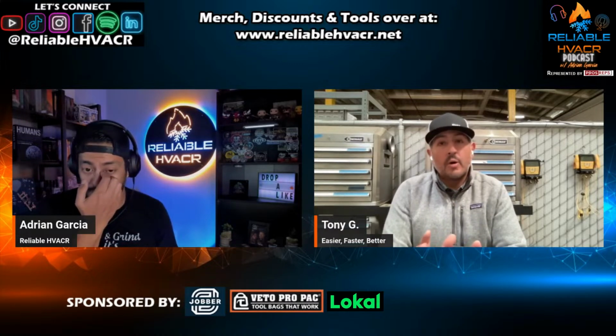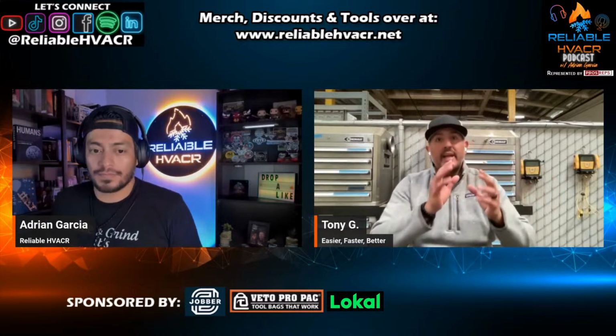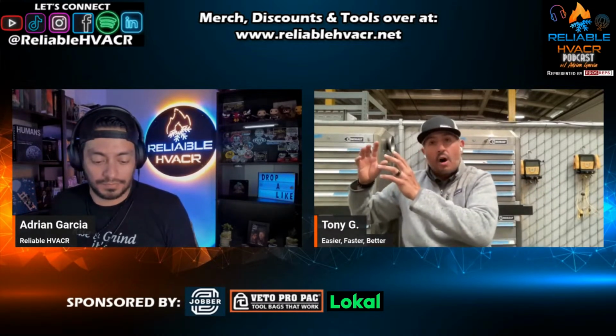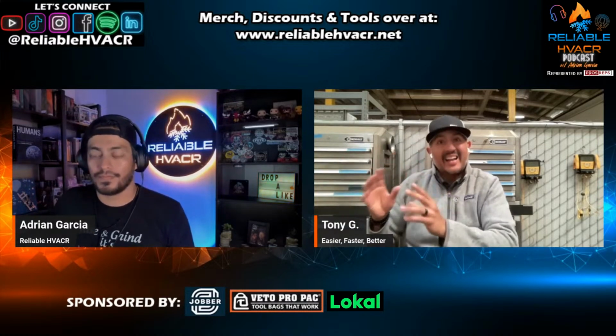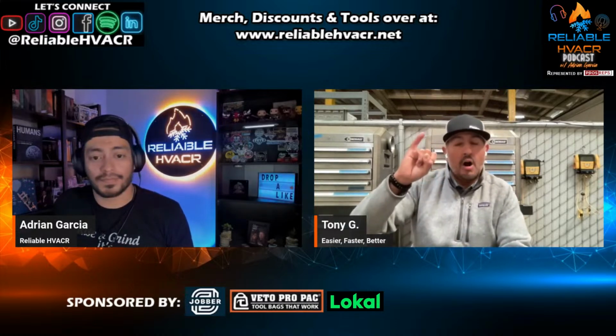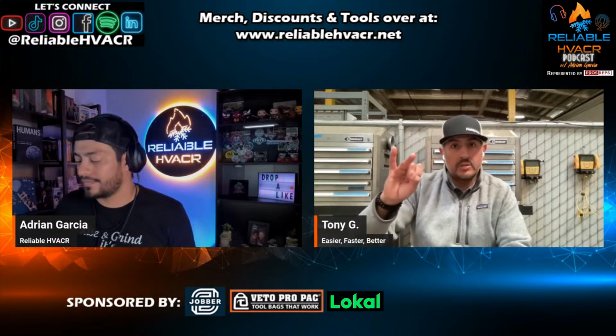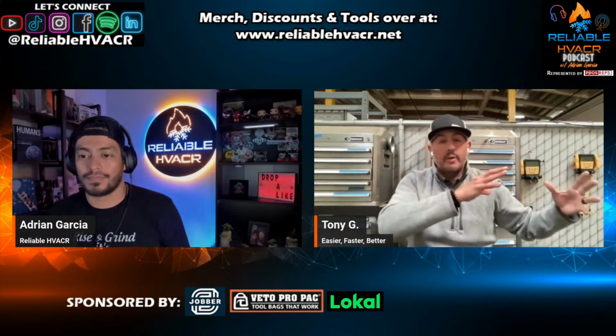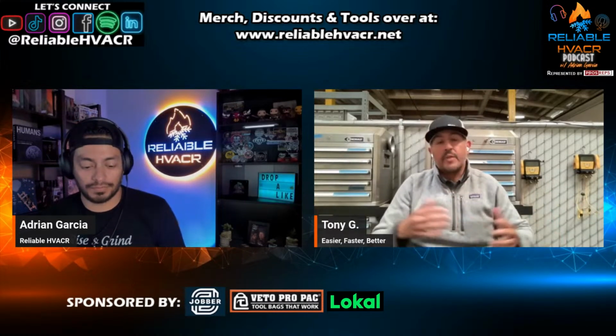And for those that were in the field when we had to transition from R22 to 410A, this transition from 410A to the R454B or things like that is a lot easier than that older transition. Why? Because the pressures aren't different. We're still dealing with the same pressures. We're still dealing with the same temperatures. We're still dealing with the same POE oil. That was not the case when we went from 22 to 410A. Pressures went way up. Oil was different, all that stuff.